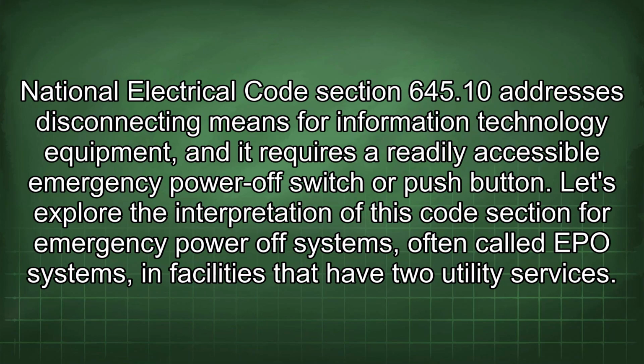National Electrical Code Section 645.10 addresses disconnecting means for information technology equipment, and it requires a readily accessible emergency power off switch or push button. Let's explore the interpretation of this code section for emergency power off systems, often called EPO systems, in facilities that have two utility services.